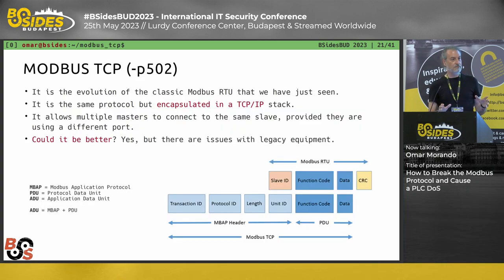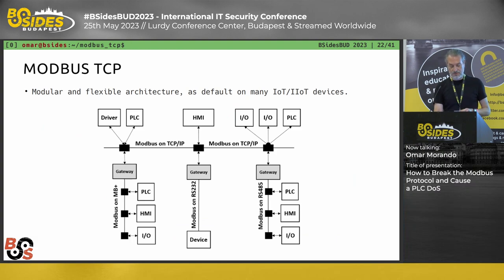The structure of Modbus TCP is the same as the Modbus serial communication protocol, just encapsulated in a TCP/IP stack, but the protocol structure is absolutely the same. We have different versions of the protocol integrated using gateways. For example, a simple device using Modbus on RS-485 or RS-232 can communicate with Modbus TCP through a cheap gateway that adapts the physical layer, letting me interact with that simple device. That's why Modbus is very common in OT plants.